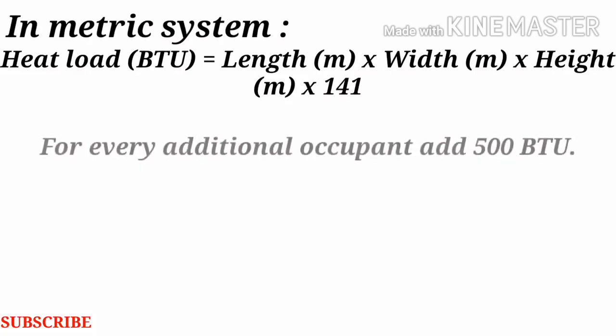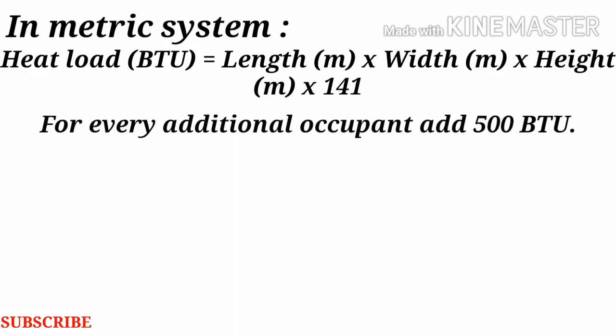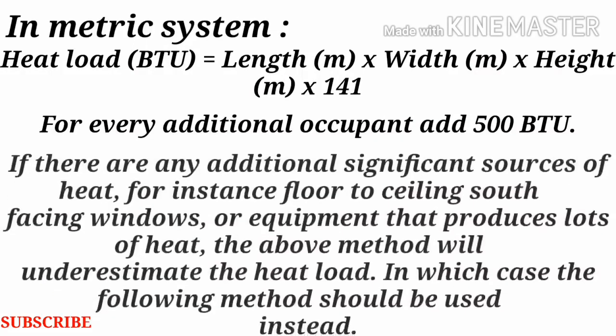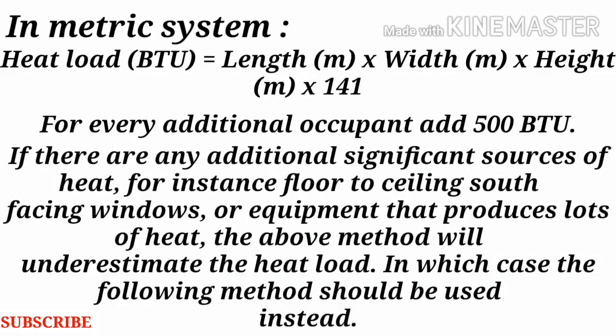For every additional occupant, add 500 BTU. If there are any additional significant sources of heat — for instance, floor-to-ceiling south-facing windows, or equipment that produces lots of heat — the above method will underestimate the heat load, in which case the following method should be used instead.